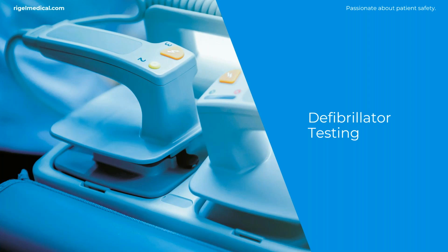So that brings us on to defibrillator testing and how we go out in the field and perform performance tests, not electrical safety tests, but performance tests on defibs and what's required. Ultimately, this comes down to the OEM on what they decide should be tested. We can introduce other tests as long as it doesn't affect the performance of the AED.